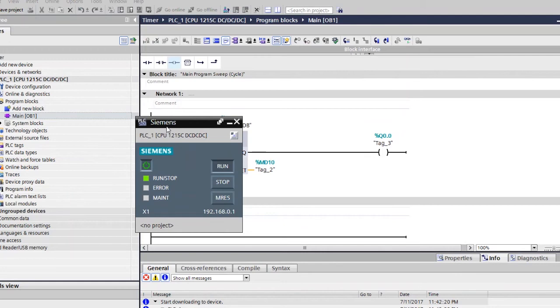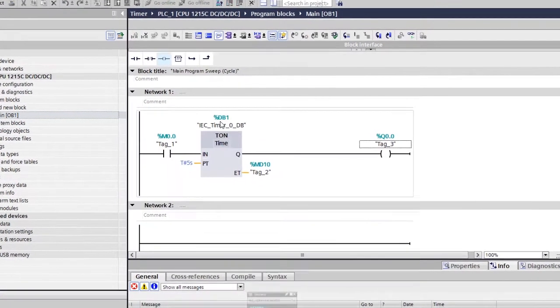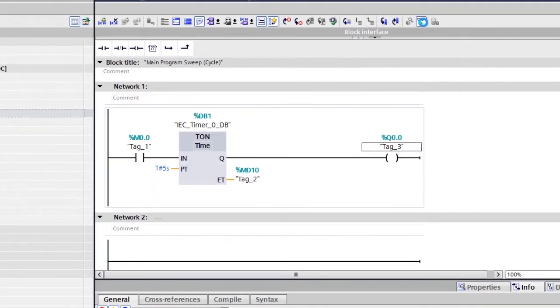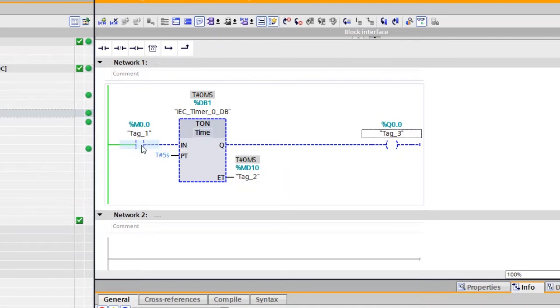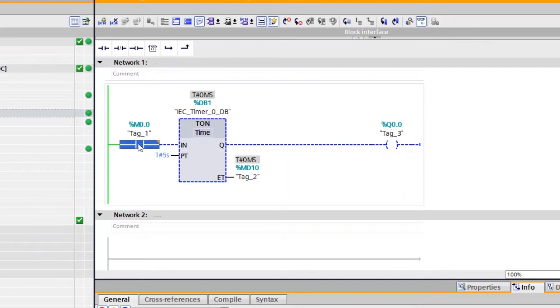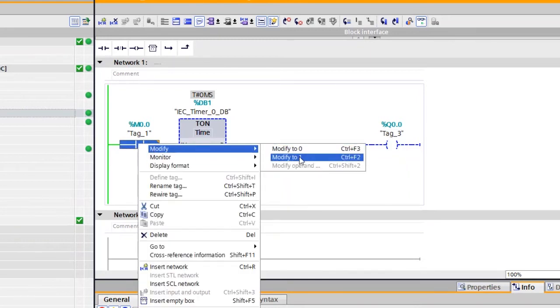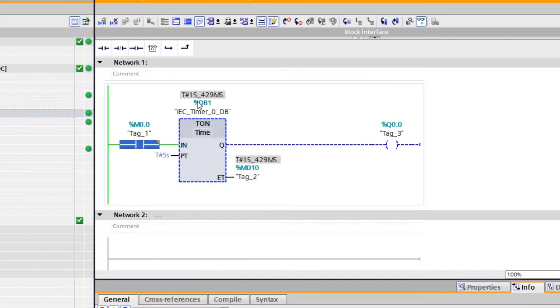Minimize this window and click the Monitor option at the top. Now you can test this TON timer. The moment I turn this instruction ON, the timer starts counting, but there is no output yet because this is an on-delay timer. Once the preset time is reached — after five seconds — the output will turn ON. Right-click, Modify, set to 1. Now you can see the timer starts: two seconds, three, four, five — there you go, the output turns ON.